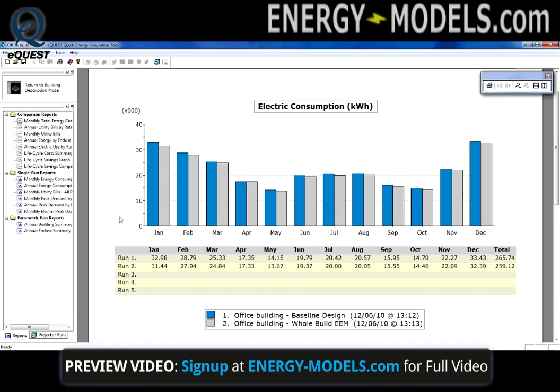In this case we're going to look at the reports in more detail. Starting with the comparison report, we have the monthly total energy consumption. The main parameter change between these two runs is there is a variable volume fan in the second run, therefore we see the greatest savings in the winter months when the air flows are much lower in the variable volume system.